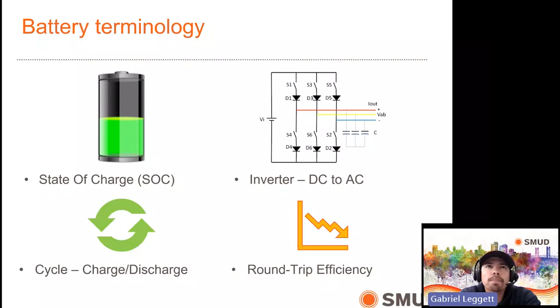Round trip efficiency is another data point you want for your battery system, and it affects the economic calculation of whether a battery energy storage system is right for you. There are losses in the system, so you don't get back all the energy you stored. If you store 10 units of energy, you'll only get back about 8.5 or maybe 9 units. So we see round trip efficiencies roughly about 85%. Some newer systems claim 89 or 90%, but just know you will experience some losses and won't get back all the energy you store during the day.